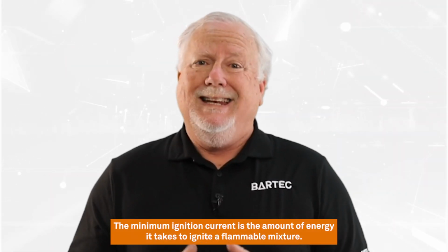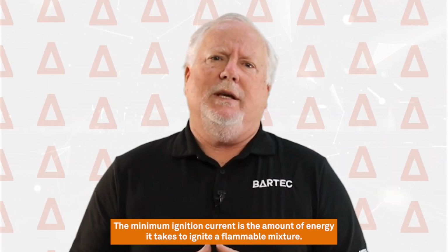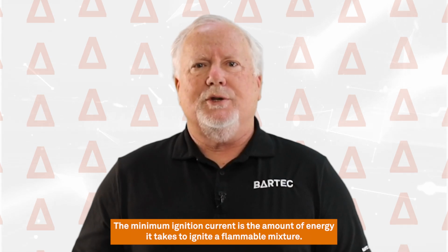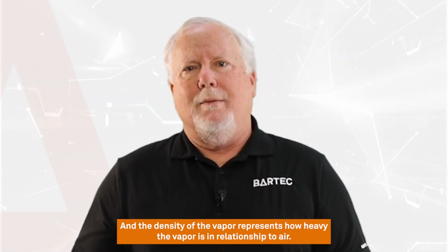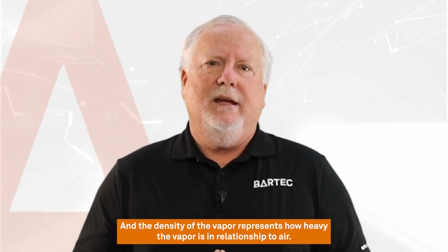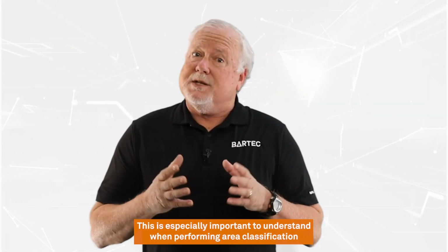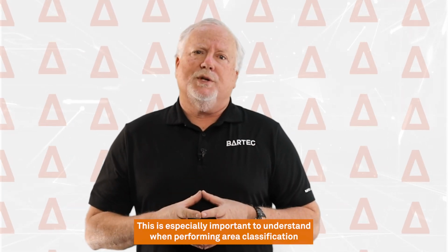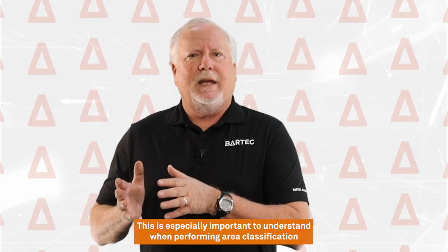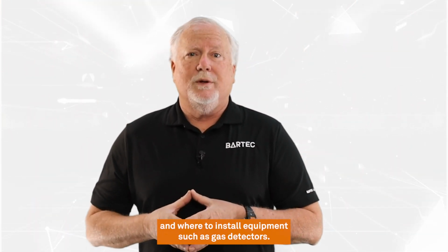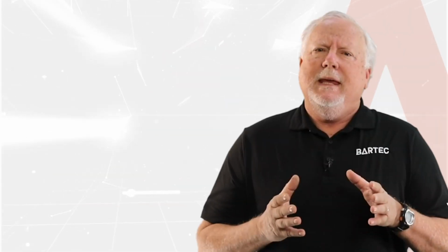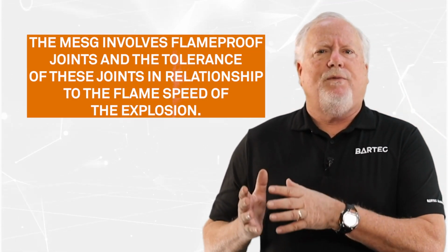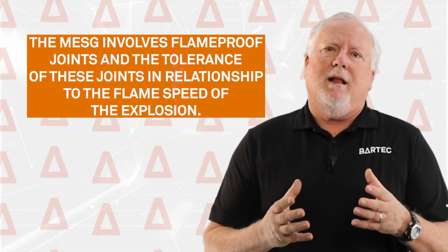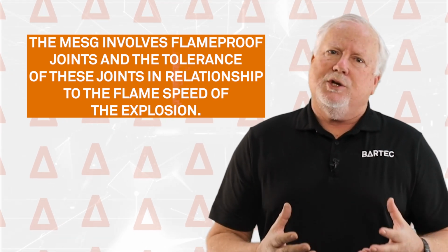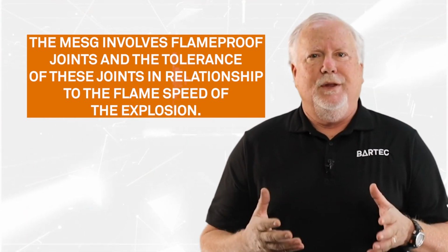The minimum ignition current is the amount of energy it takes to ignite a flammable mixture, and the density of the vapor represents how heavy the vapor is in relationship to air. This is especially important to understand when performing area classification and where to install equipment such as gas detectors. The MESG involves flame-proof joints and the tolerance of these joints in relationship to the flame speed of the explosion.